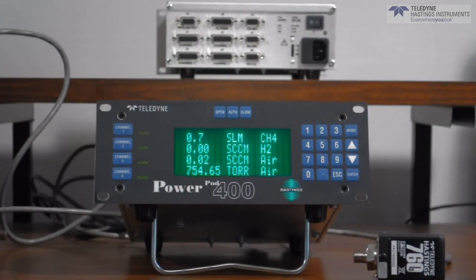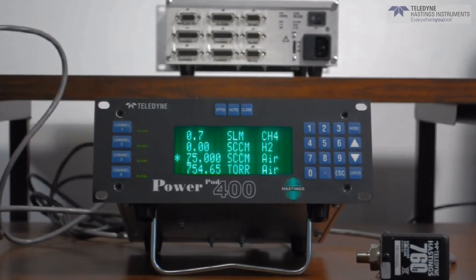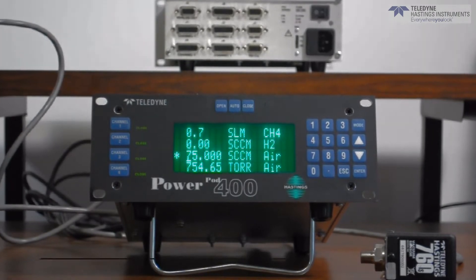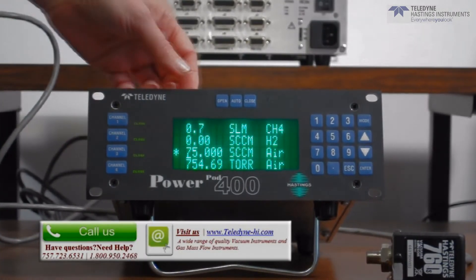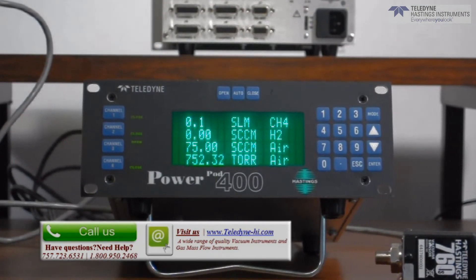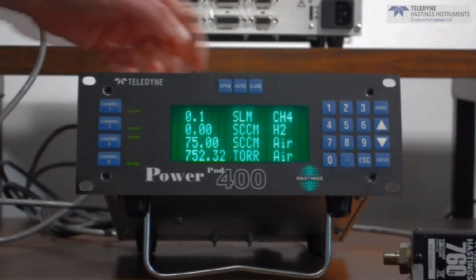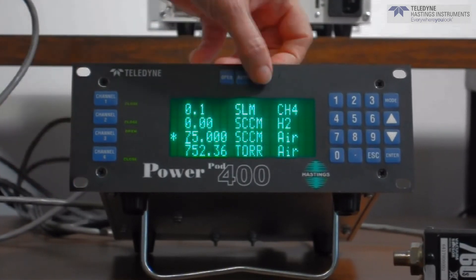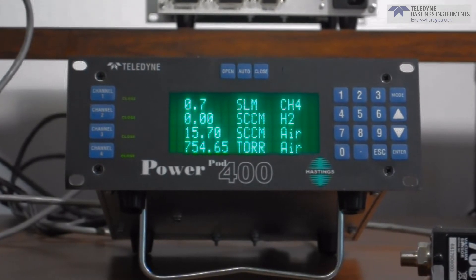Let's take a look at how this would work. If you'd like to address channel 3, press the channel button. You'll notice that an asterisk appears telling you that this is the channel in play or being addressed. To open the valve, perhaps to purge the line, press open. You can both hear and see the valve response. To close the valve, press the channel button again and press close. You can both hear and see the valve response.